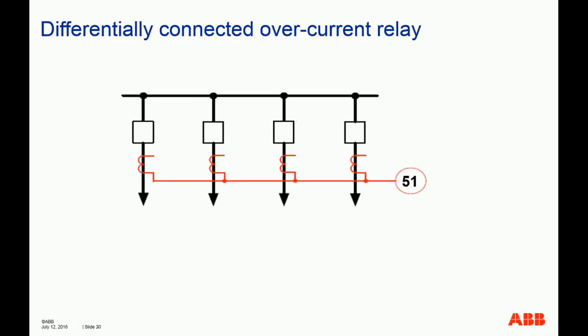So what is the differentially connected overcurrent relay? It's very simple. It's the overcurrent relay, 50 or 51, depending, where you sum the CTs externally through hard wiring and bring that sum into the relay. That's all. So basically it's an overcurrent relay, but because you externally sum all the CTs, it behaves as a differential relay.